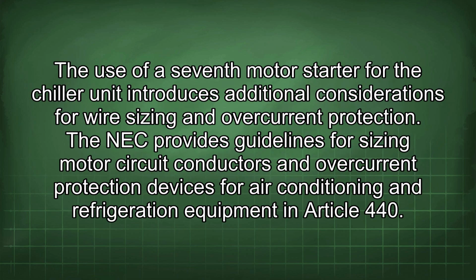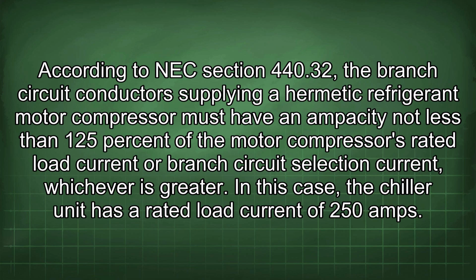The use of a 7th motor starter for the chiller unit introduces additional considerations for wire sizing and overcurrent protection. The NEC provides guidelines for sizing motor circuit conductors and overcurrent protection devices for air conditioning and refrigeration equipment in Article 440. According to NEC Section 440.32, the branch circuit conductors supplying a hermetic refrigerant motor compressor must have an ampacity not less than 125% of the motor compressor's rated load current or branch circuit selection current, whichever is greater.